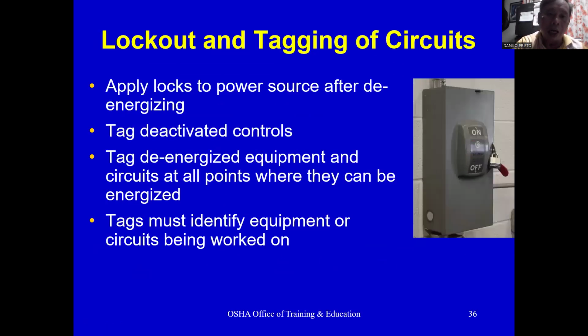Lockout and tagging of circuits. Apply locks to the power source after de-energizing. Tag deactivated controls. Tag de-energized equipment and circuits at all points where they can be energized. Tags must identify the equipment or circuits being worked on. Okay, based on the picture.